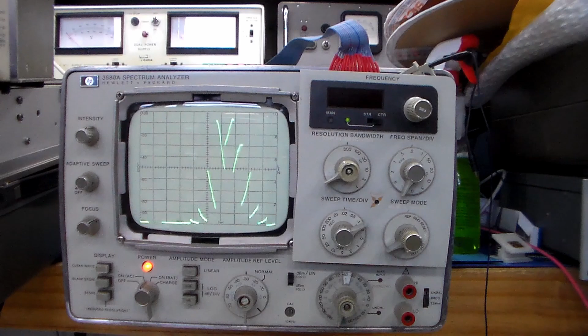So I've been able to narrow down the issues with both of these units by swapping over the digital boards between the two, and the issue of lack of sweep on the unit that is pictured at the moment has now changed to the issue that I described previously, and similarly the digital board placed in the other unit now gives the same symptom that was in this unit, being basically no signal, or a very small signal, a little bit of noise on the baseline and nothing else. So I can be pretty confident that in both cases the digital boards in these units are the cause certainly of the sweeping issues that we have.